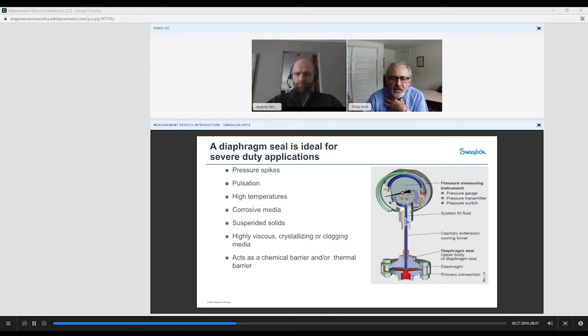Then the system fill media, as I talked about, is inside. The various components that we talked about earlier in the presentation are contained in the gauge. So where would you use this? If you have a lot of pressure spikes in your system, this will reduce the effects of the pressure spikes on the gauge. You can also liquid fill the gauge itself to dampen the movement and help provide lubricity and other things. So where you have pulsation, where it's pulsing back and forth, this can help dampen the effects on all those little gears that I talked about in that movement inside.